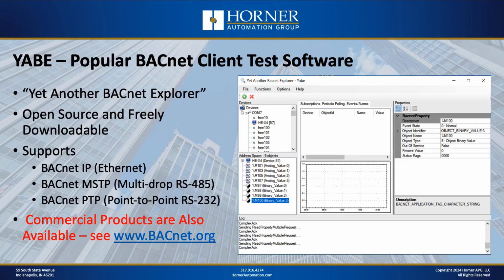But if you're just looking for a down and dirty utility that is effectively open source and freely downloadable, then a good place to start is something called YABE, which stands for Yet Another BACnet Explorer. And you can download that, again, freely from the web. And there are better tools, I'm sure, and there are commercial tools that come with support. So I'm not saying don't use those, but a good place to start is with YABE. And in the case of YABE, it supports both BACnet IP and BACnet MSTP. So if those are the networks you want to support, then it's a tool that you can use for some basic testing.